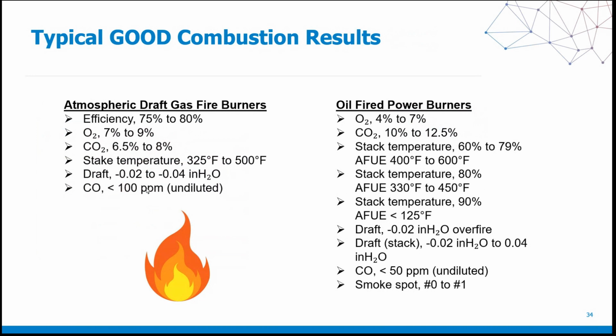Now, I know that you're going to say there are some manufacturers that allow you to have 200 ppm under high fire, 400 ppm on the stack under high fire. That's all well and good. But general industry guidelines are 100 ppm or less in the stack of CO under steady state running conditions. So always keep that in mind.